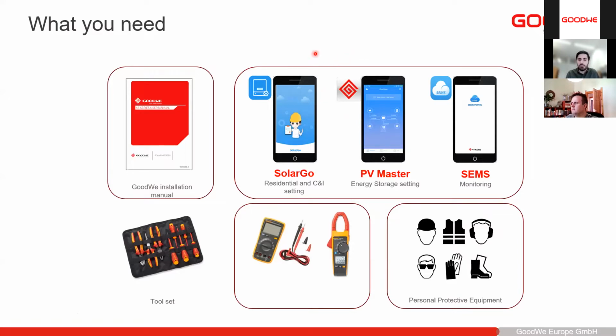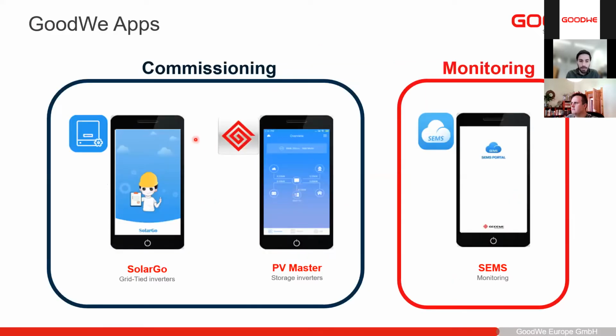And for commissioning, we also have a few different softwares to help you with that. It might look a bit complicated to have 3 different apps, but to make it clear, I will show you later on. But basically, we have 2 for commissioning and 1 for the monitoring. For commissioning, we provide it depending on whether it's a grid tie inverter only, or if it has any storage features. The Solar Go is used for grid tie inverters only, and PV Master for all types of storage inverters. That means even the battery inverters, AC coupled, and hybrid inverters. And the SEMS is only for monitoring.